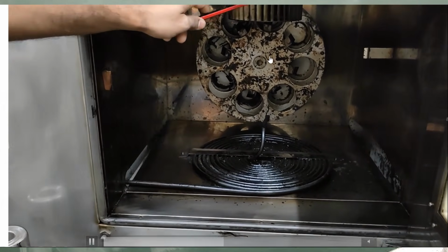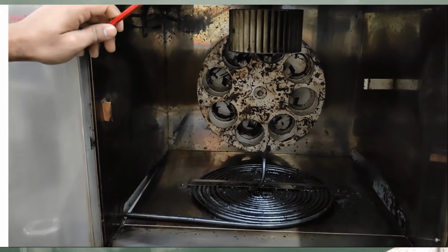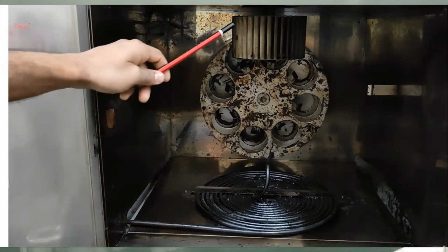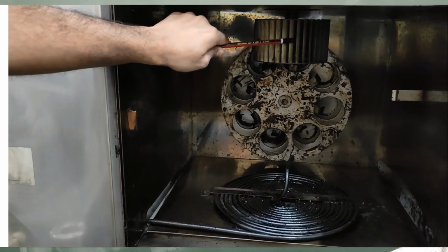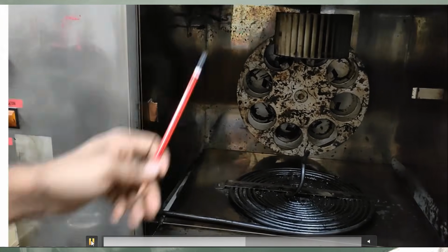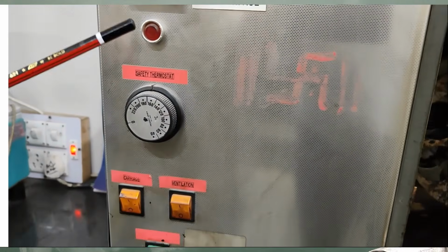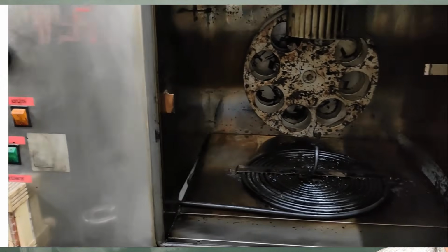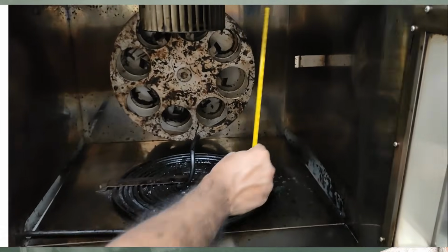There is a fan here, fan motor here, and at the top of this oven, sometimes it is at the top of the oven, sometimes it is inside, which runs at 1725 RPM. The fan and heater will be on only when the oven door is closed. The oven has a thermostat to maintain the air temperature at 163 degrees centigrade, and a thermometer that can be hung either through the ceiling or it can be put in the clip.